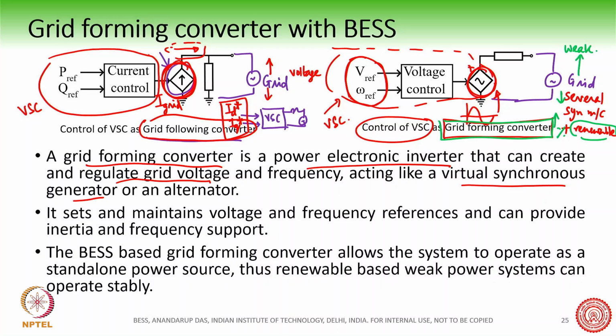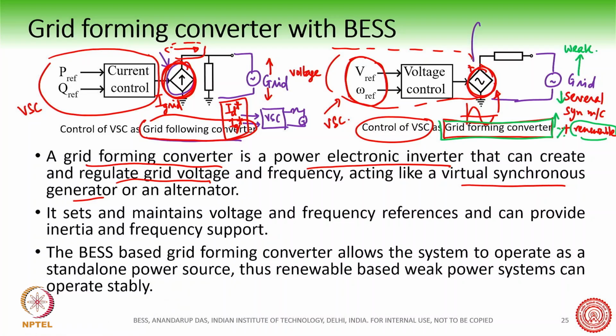And who gives it the active power? Of course, we have the battery, BESS. BESS is the energy source to this voltage source converter. So a BESS based voltage source converter can act as a grid forming converter. It sets and maintains voltage and frequency references, and can provide inertia and frequency support.